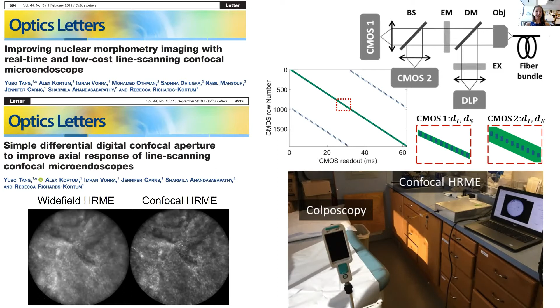But when we image columnar tissue, here's what we could do with our old HRME, the non-confocal version. Here's that same exact spot with this differential line scanning approach, and you can see the much better rejection of multiple scattered light, better image contrast, and the ability to recognize the openings of these glands in columnar tissue. We're just starting a study now to look at whether we can improve our diagnostic performance using a combination of these imaging approaches. So how do we get at the limited field of view challenge?